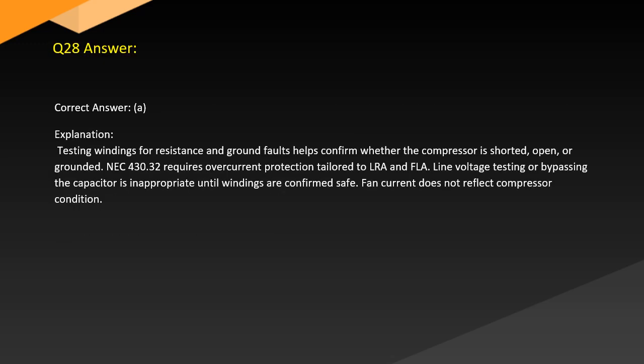Answer. Correct answer. A. Explanation. Testing windings for resistance and ground faults helps confirm whether the compressor is shorted, open, or grounded. NEC 430.32 requires overcurrent protection tailored to locked rotor amps. Line voltage testing or bypassing the capacitor is inappropriate until the windings are confirmed safe. Fan current does not reflect compressor condition.